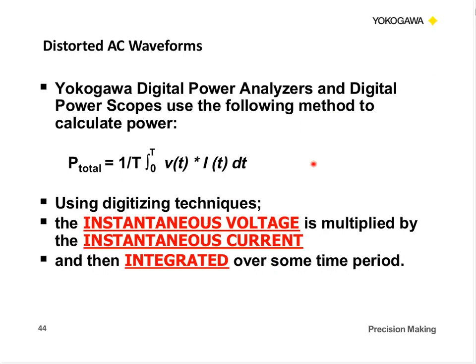So remember how we calculate power. We digitize that incoming voltage and incoming current. We're going to repeat this so you know what we're doing. We take the instantaneous voltage times that instantaneous current, accumulate them over a time period, integrate that, and multiply by 1 over T. And so we get a true power measurement regardless of the wave shape.